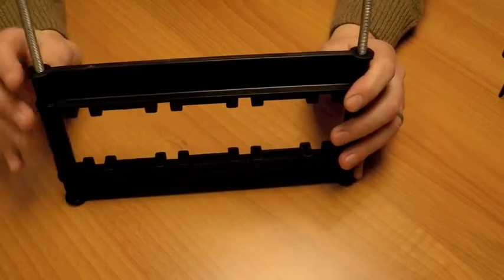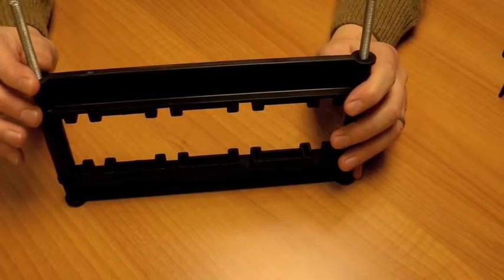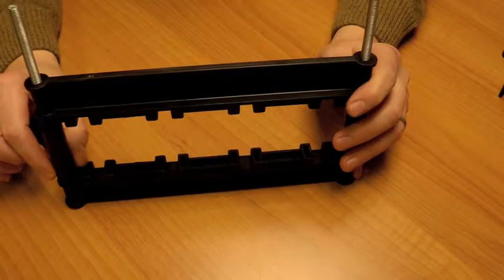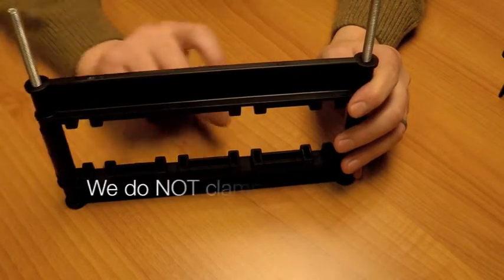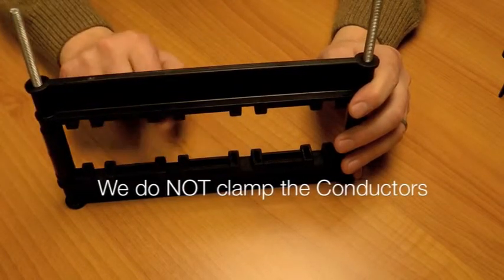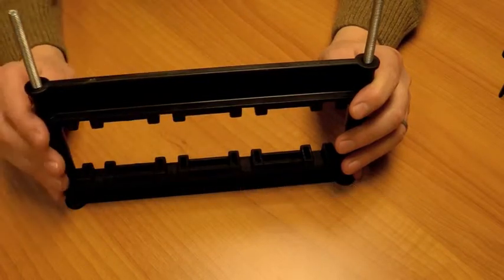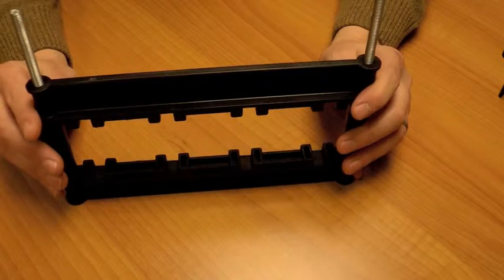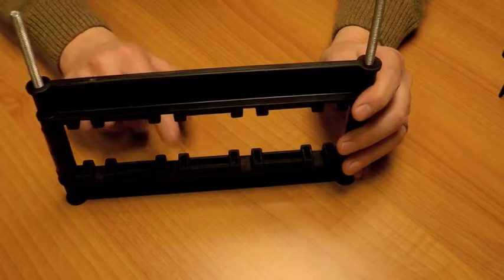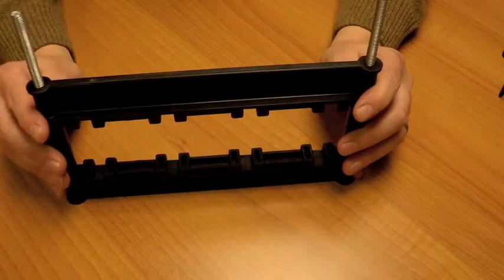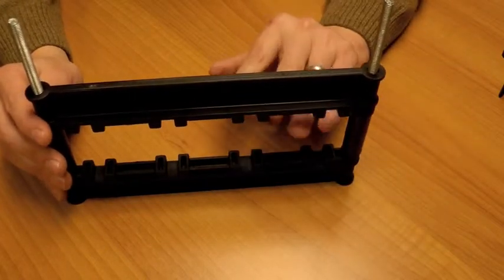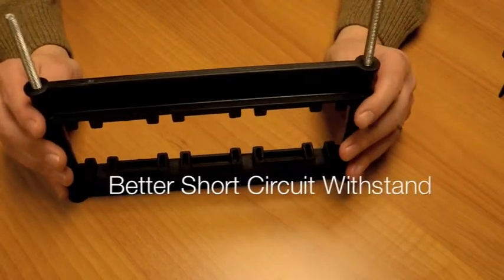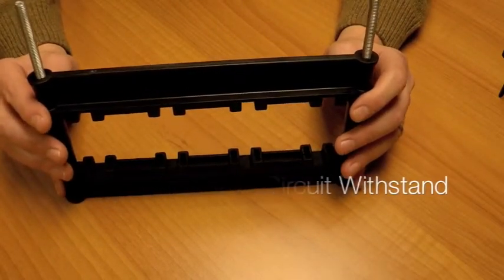As you can see, we actually tighten down onto the spacers. Termate do not clamp the conductors within the bus bar support assembly. We believe that when a short circuit happens, the slight freedom of the bus bars allows the bus bar supports themselves to better withstand the forces generated under these conditions.